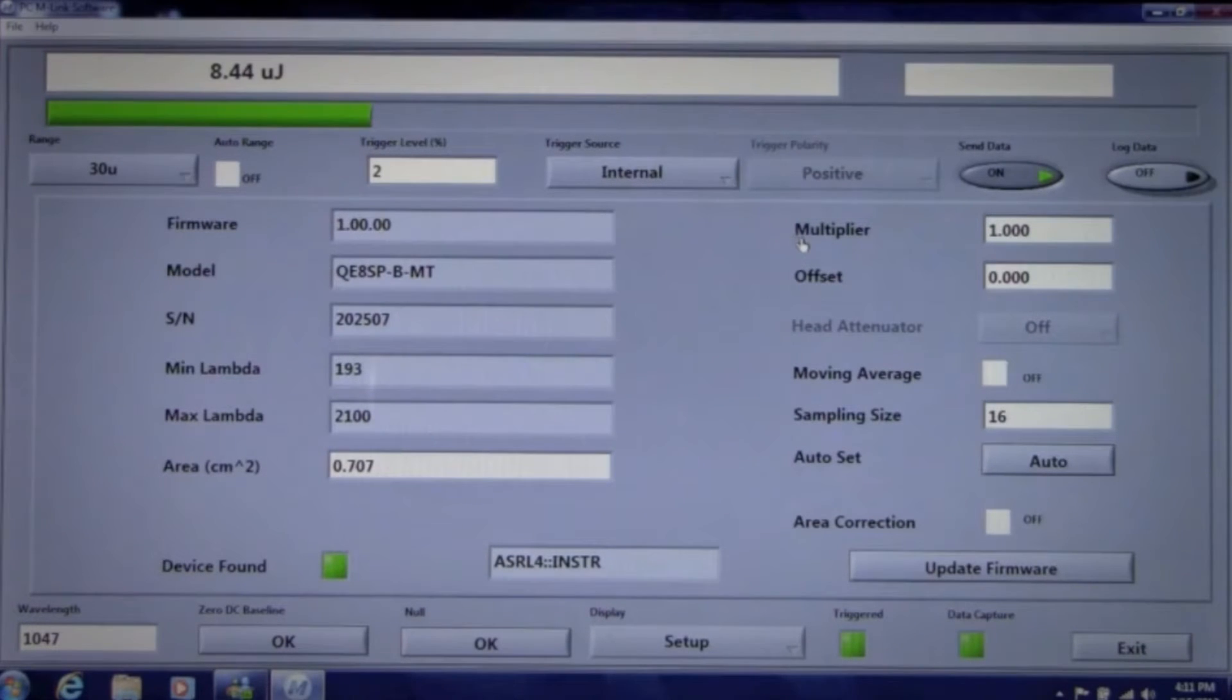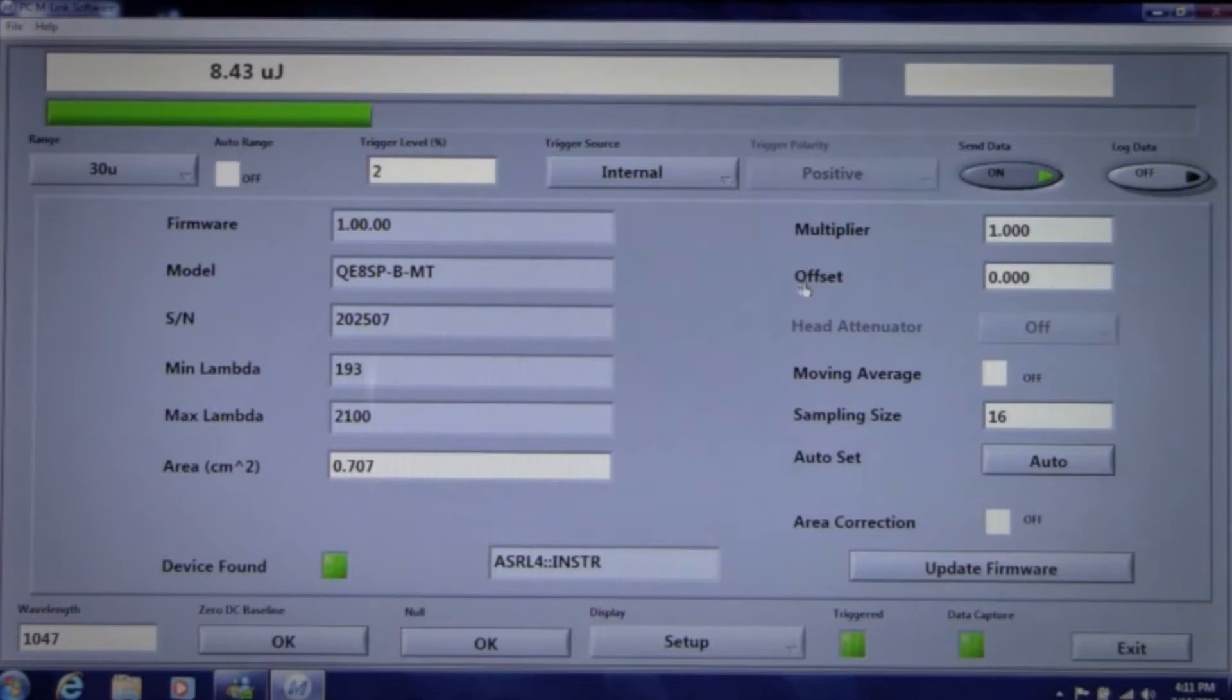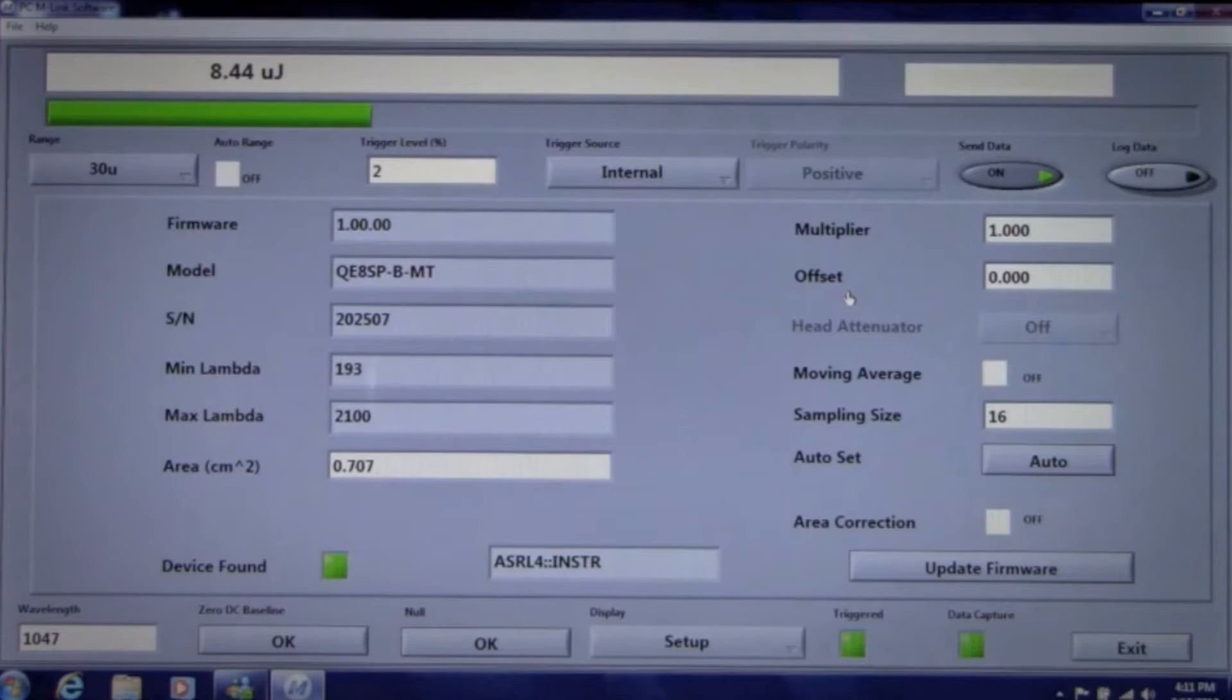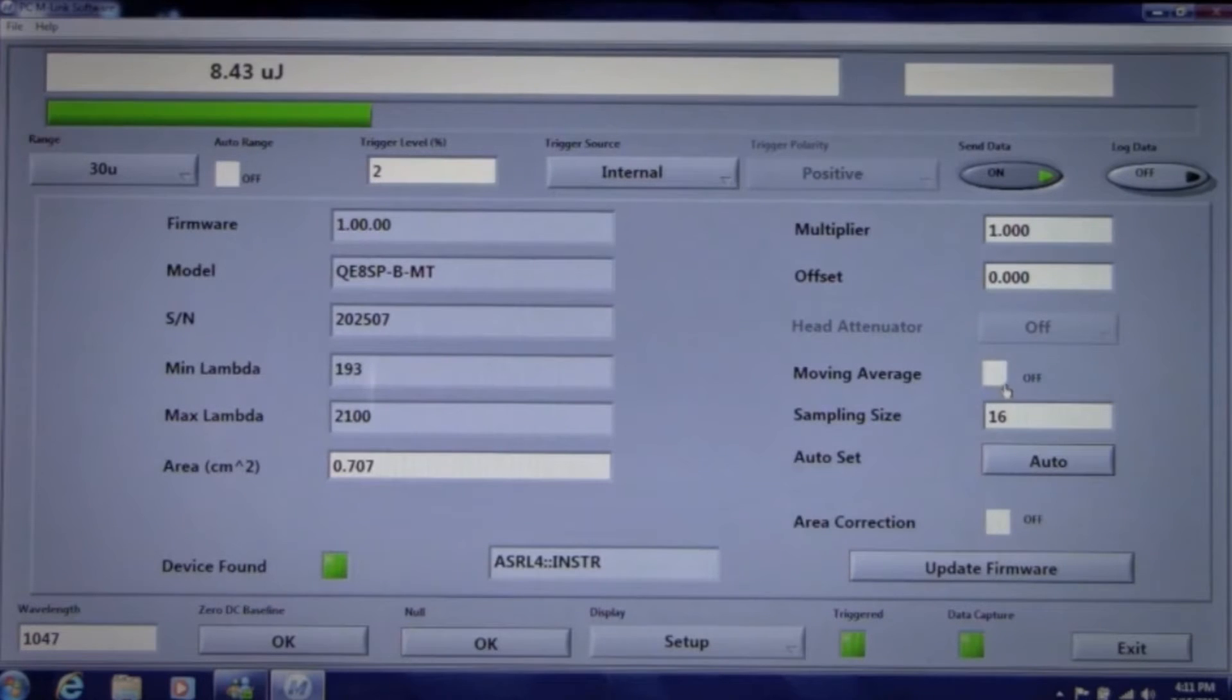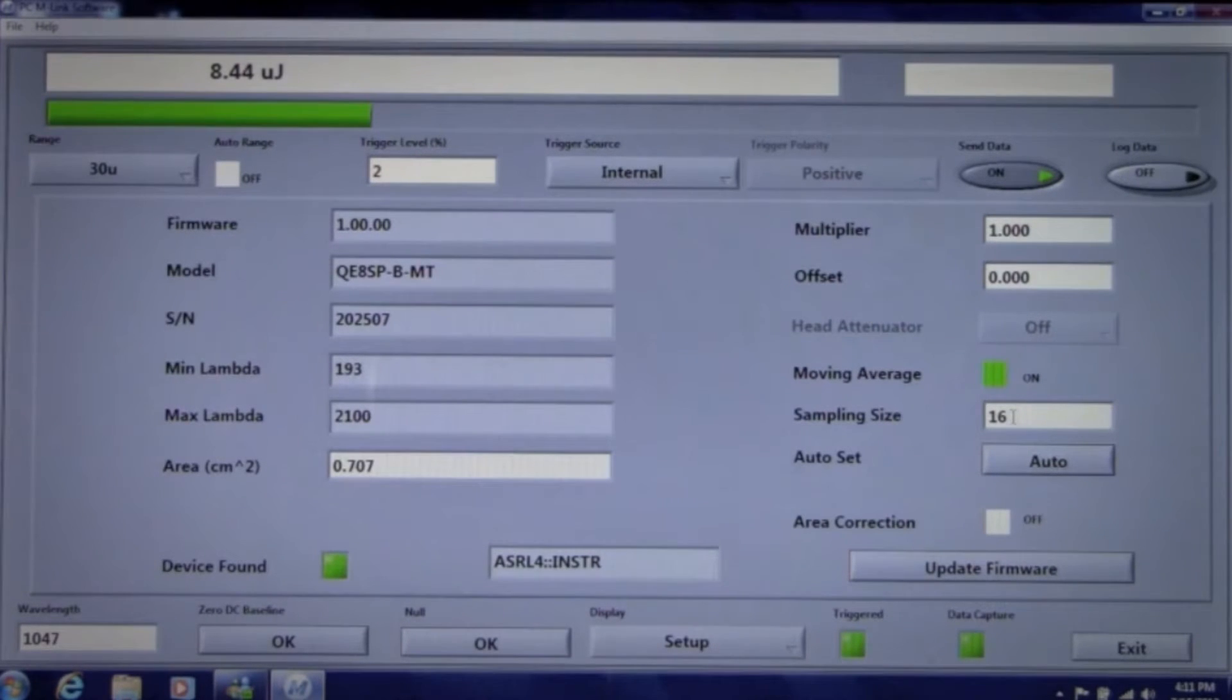You can also enter a multiplier or an offset to compensate for a particular optical setup. You can select moving average and sample size if you want to stabilize your readings.